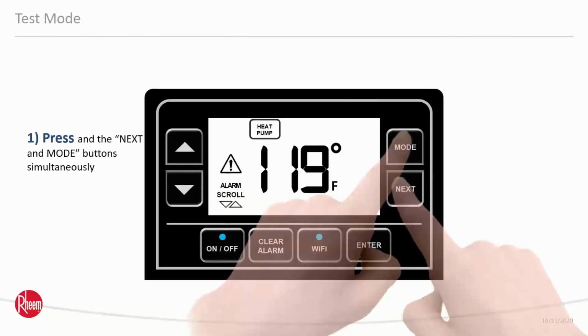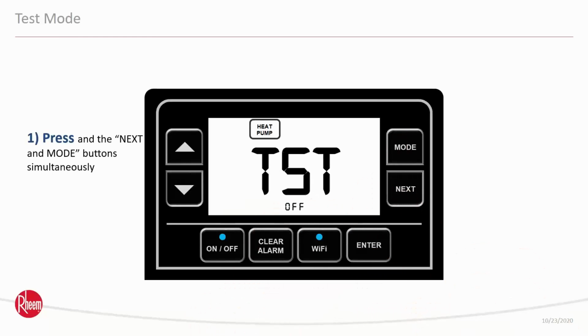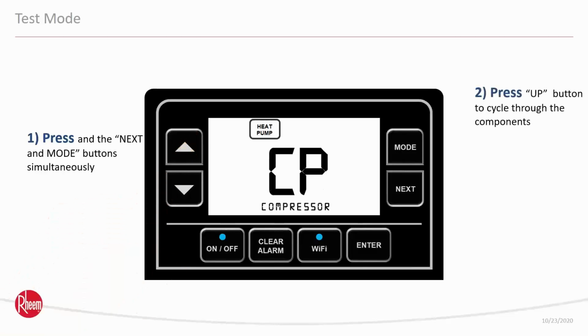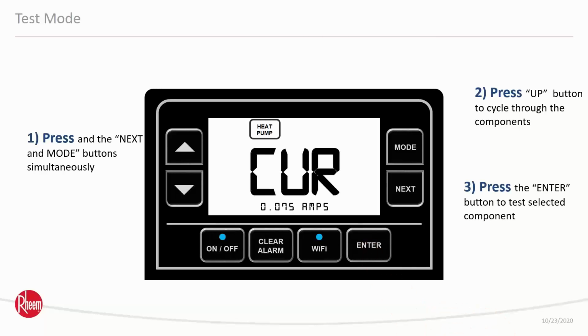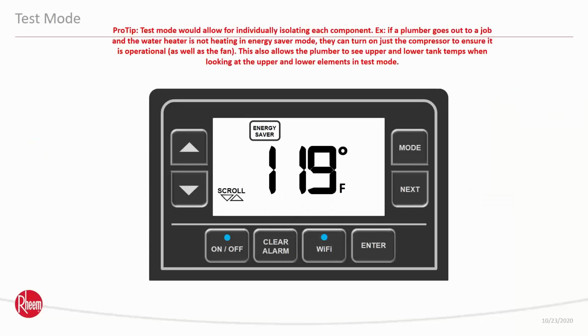Test mode. This is going to be more for your contractor when he comes in there. This is where he's going to test the heat pump. You press the up and down, you can step through, check your compressor. Hit enter, it's going to tell you how many amps, at 0.075 amps, that compressor is pulling at that point in time. It'll tell you exactly what it's doing. Test mode is going to allow for individually isolating the components.